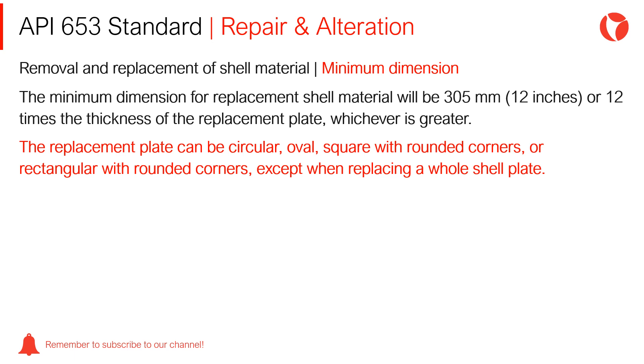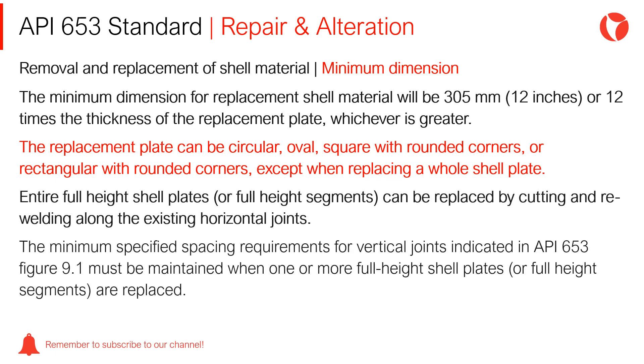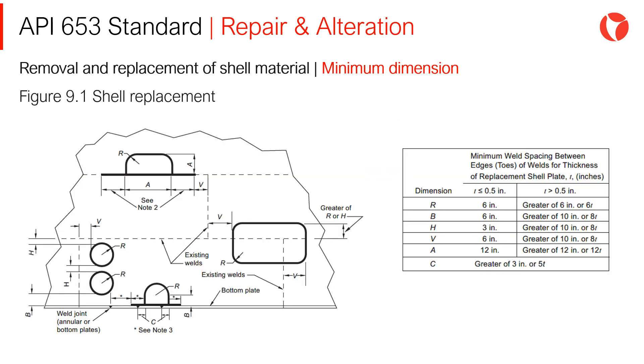The replacement plate can be circular, oval, square with rounded corners, or rectangular with rounded corners, except when replacing a whole shell plate. Entire full-height shell plates or full-height segments can be replaced by cutting and re-welding along the existing horizontal joints. The minimum specified spacing requirements for vertical joints indicated in API 653 figure 9.1 must be maintained. Figure 9.1 shows the minimum requirements for thicknesses and distances when replacing parts of the shell or entire shell plates.